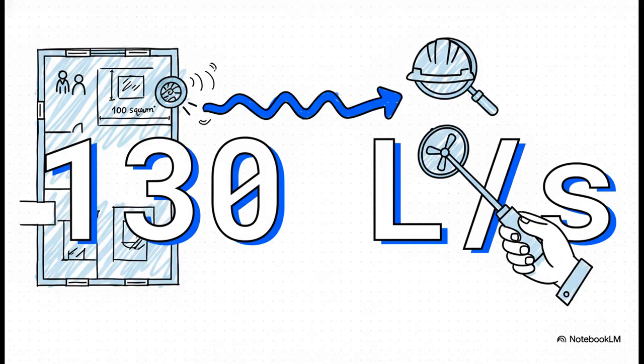So let's make this real. Imagine a typical office, 10 people, 100 square meters. You run the numbers, and you get 130 liters per second of fresh air. That's it. That's the exact number an inspector is going to look for in your paperwork, and then they're going to walk out to the site with their meter and check it.